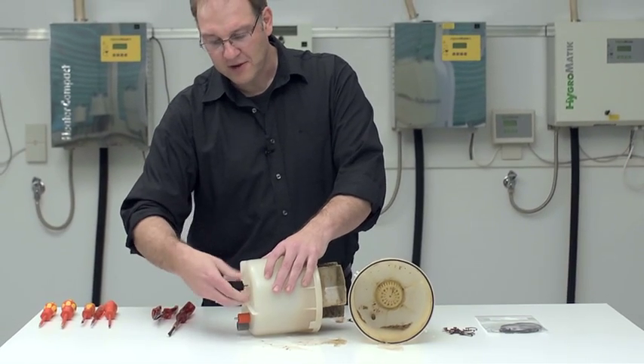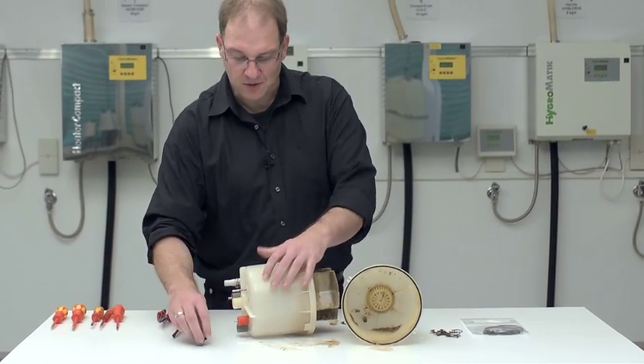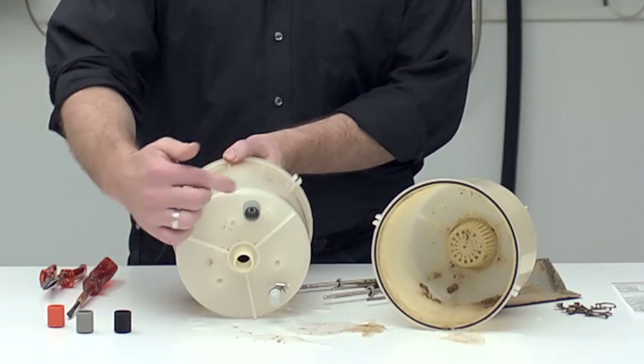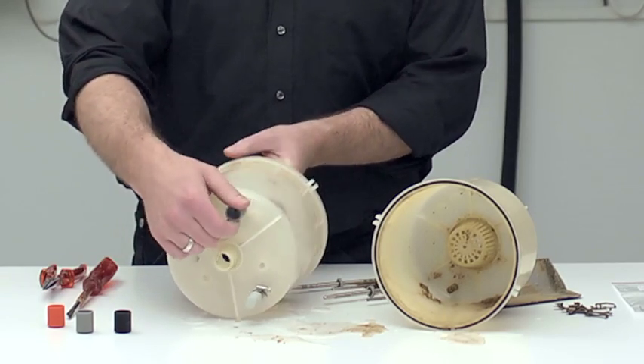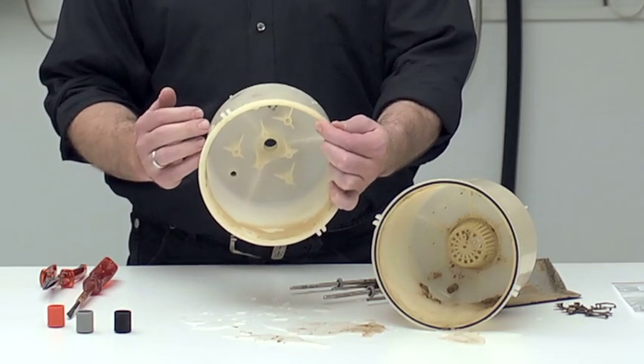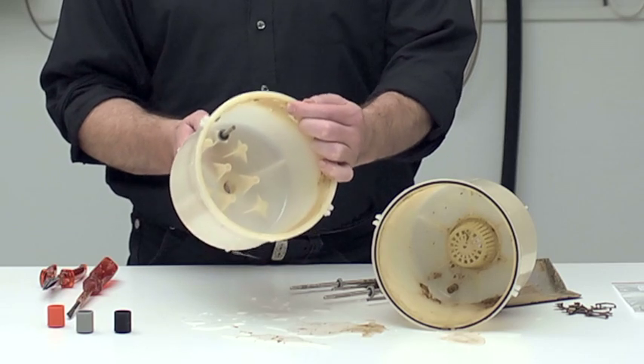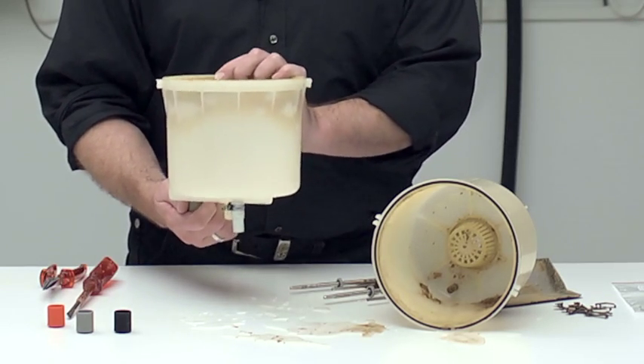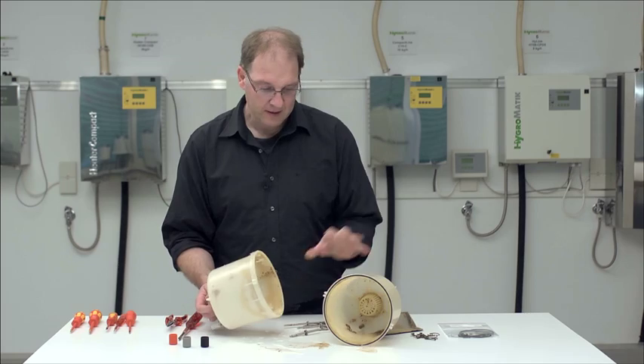This knurled nut can be loosened simply by manual force, then press it to the front, and you can see that there is another one, which is the sensor electrode, which is just a small metal pin that can determine the maximum level of water in the cylinder. This electrode does not wear down and does not need to be replaced, but you should disassemble it and include it in the cleaning.